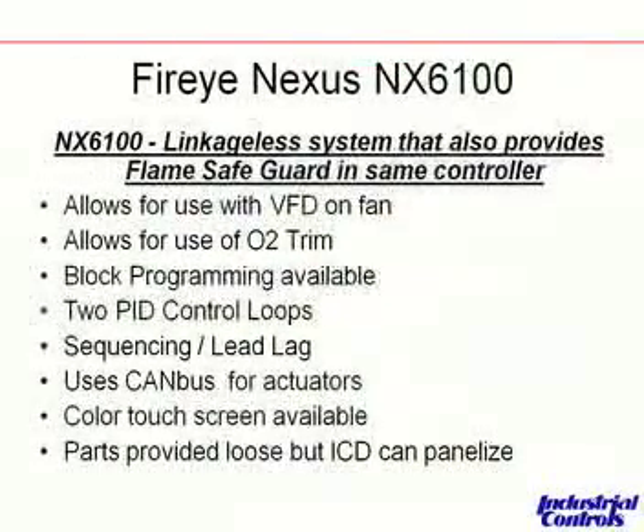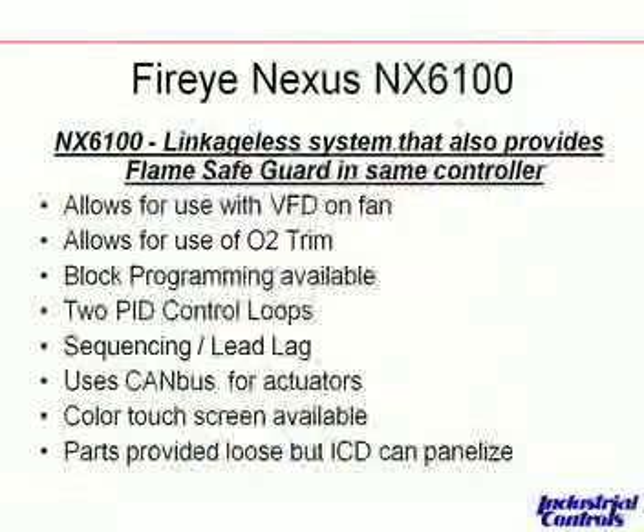The FireEye Nexus 6100 is their higher-level linkageless control system, and it provides the flame safeguard already integrated into it. It has very similar features to the PPC-6000 as far as VFD, O2 trim, and block programming. One thing it offers that the others don't is a color touch screen, which can be used for up to four boilers and can even be mounted in a boiler operator's office, with smaller displays at each boiler for trending and monitoring — amortizing your investment over four boilers instead of one.